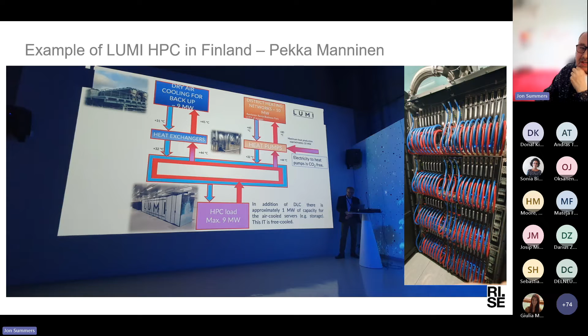The interesting thing is that the supply temperature to the IT is 32 degrees centigrade because it's liquid cooled - here's a picture of the liquid cooled technology they're using - and it returns at 44 degrees from the IT. To get it up to the 88 or 90 degrees needed for district heating, they have to use a series of heat pumps in the loop. So they own the heat pumps, but that also affects their overhead for running the compute, because the compressors are quite energy intensive.